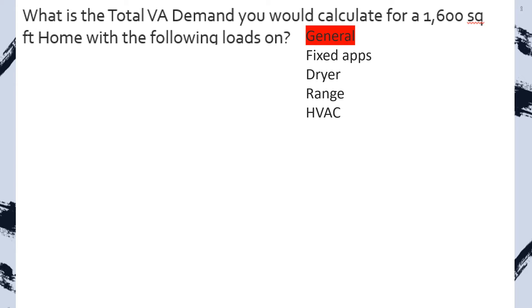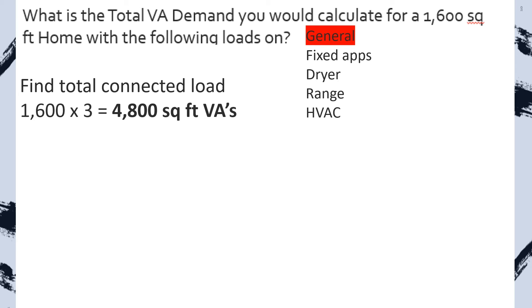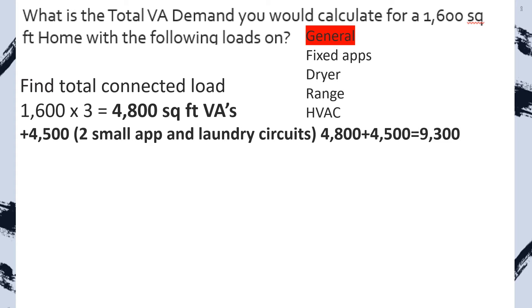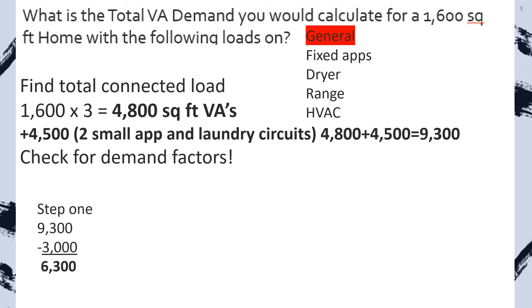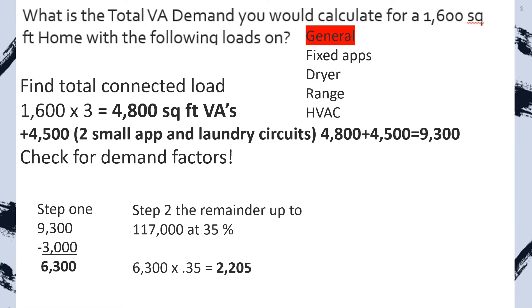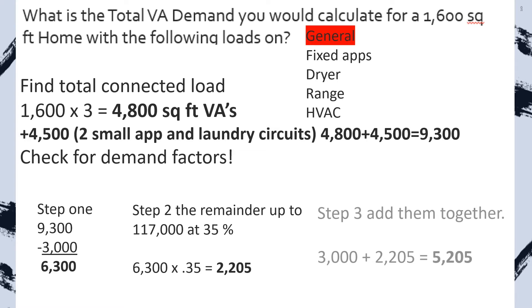Step 1 is to find our general lighting and receptacle loads. We're going to first find our total connected load. We take our 1,600 square feet multiplied by 3, which gives us 4,800 VA. Now we add on our two small appliance and one laundry circuit, which is 4,500, giving us a total connected load of 9,300. Now we check for demand factors: we take the first 3,000 at 100%, the remainder at 35%, then total them back together and put that on the right-hand side.